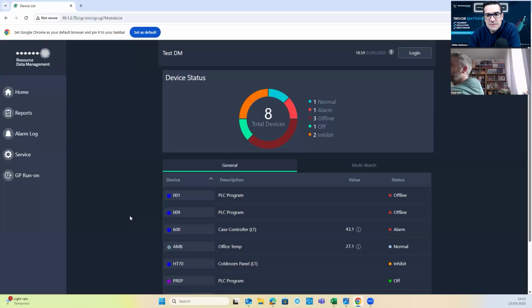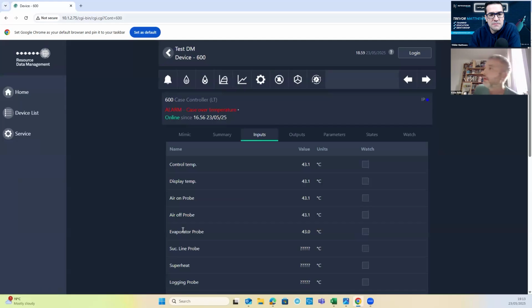And while we're doing the other controller, if that logs on, we'll be able to see it. So while that one's sorting itself out, let's have a look at the one we've just logged on. So I've switched my controller on to start with, and it's come set up by default as a case controller, as we can see. Now there's a menu on the RDM controller called type. You've got types 1 to 6 on most of their controllers, and that gives you presets, right?